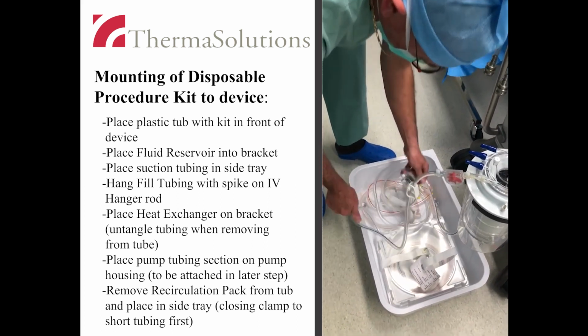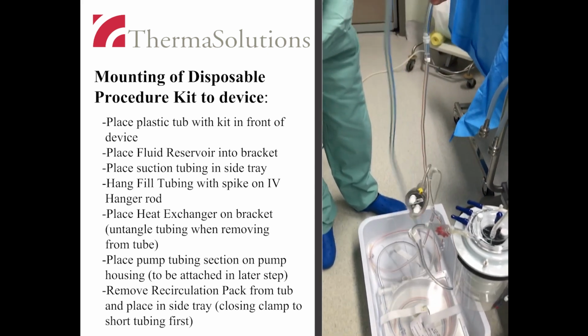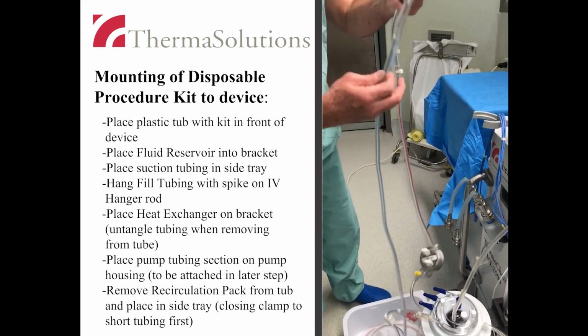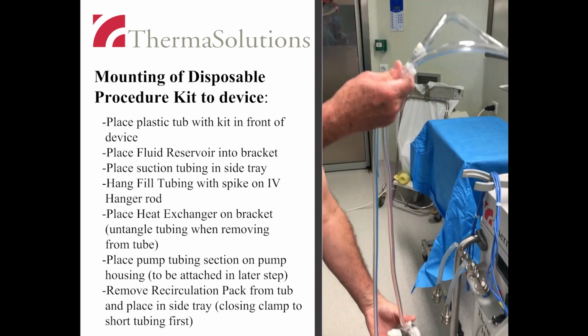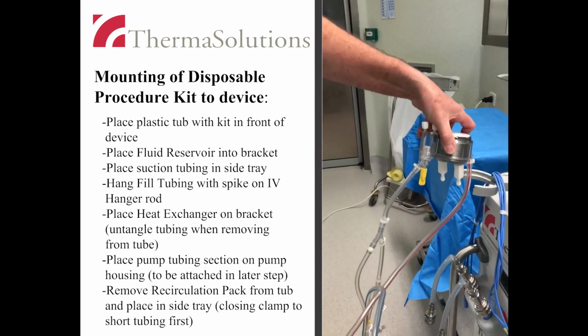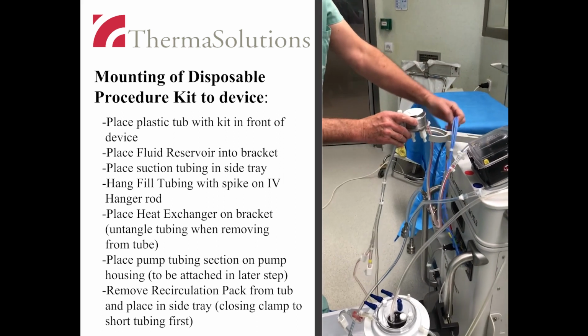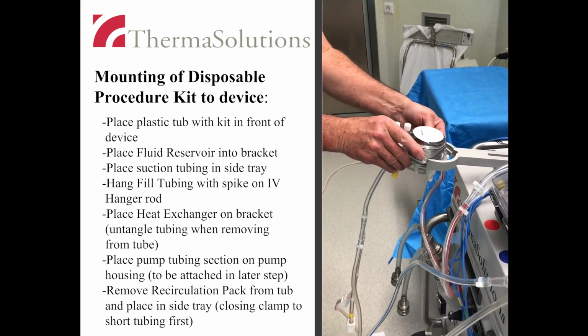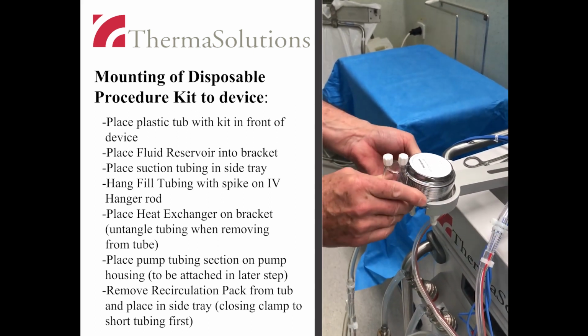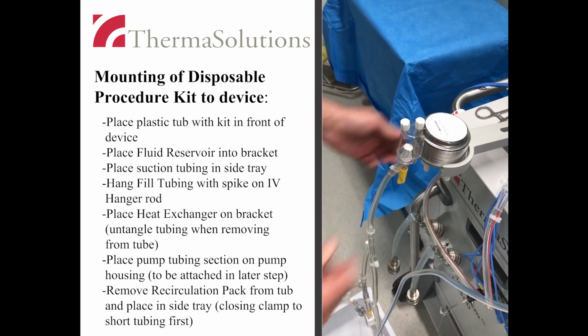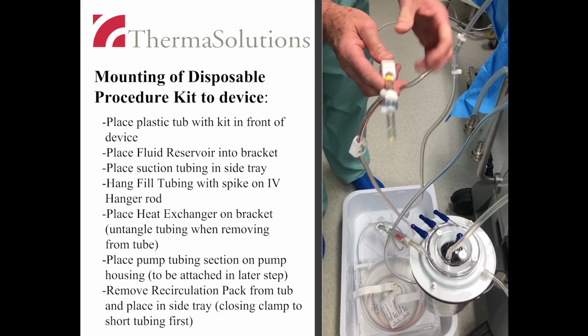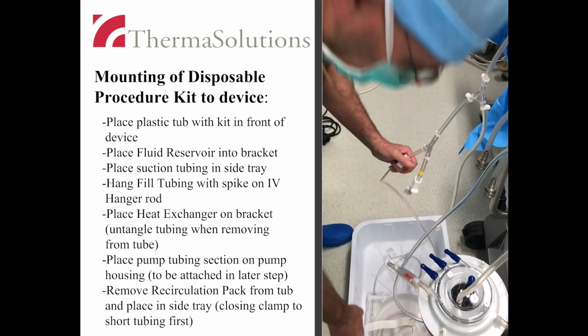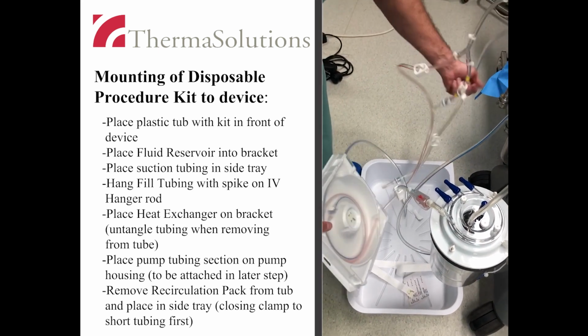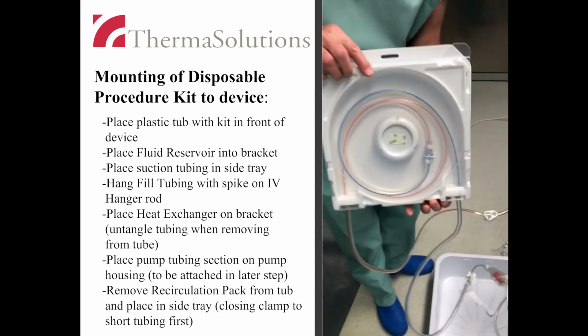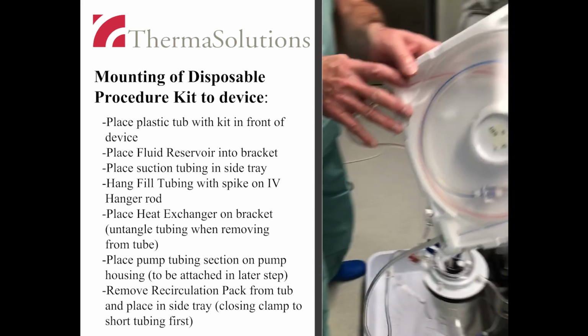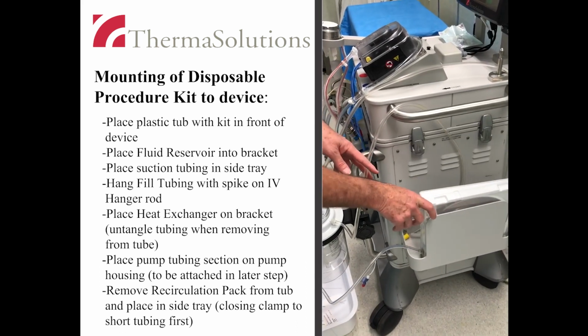Lift the heat exchanger out of the tub and make sure the tubing lines are untangled before placing the heat exchanger on the silver heat exchanger bracket. Place the tubing for the pump housing on top of the pump for attachment later. Before removing the recirculation pack from the tub, close the clamp to the shorter tubing. Place the recirculation pack in the side tray.